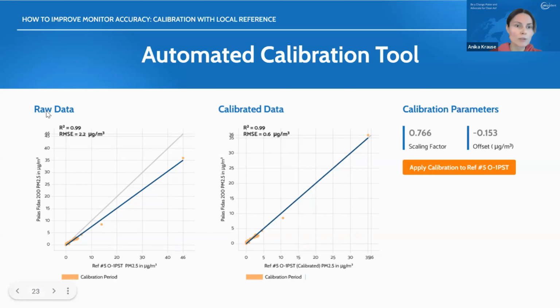The plot also gives you a measure for that, the R² value. And the R² value can be maximum 1. That means perfect correlation, perfect tracking of each other. So you see they actually track each other really well, which you also see here. And the closer this line is to this gray one-to-one line, the better the accuracy of the sensor.